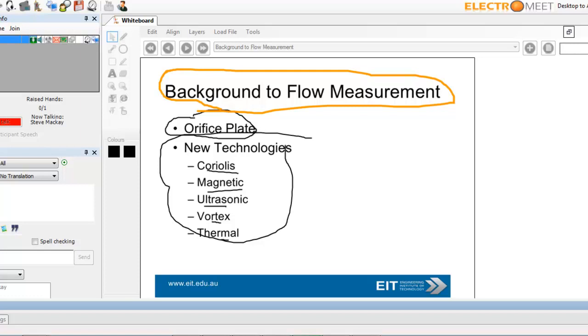But low initial cost doesn't mean total cost of ownership will be lower. It's probably going to be higher. Problems with orifice plates: pressure drop, so you lose energy. Your plate can be knocked out of position, and it's not as accurate, and efforts aren't going into technology improvements with orifice plates, and there's a limited rangeability. And occasionally, sometimes you see it installed backwards.